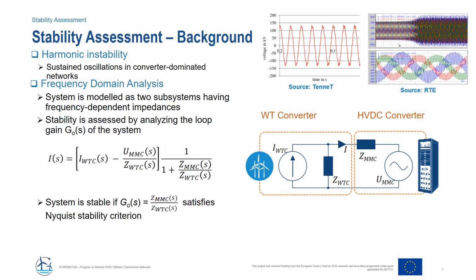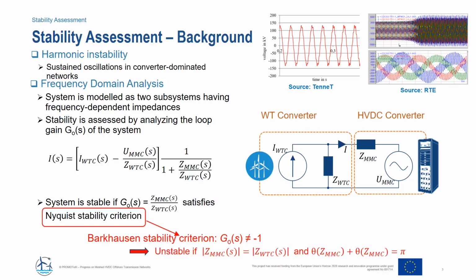The stability of the overall system is analyzed by the open loop gain G0 of the system. We say the system is stable if G0, defined by the impedance of the MMC divided by the impedance of the wind turbine converter, satisfies the so-called Nyquist stability criterion. In this implementation, we have simplified that even more to the so-called Barkhausen stability criterion. Basically, we say that the system is stable as long as G0 is not equal to -1. Furthermore, we could say that the system is unstable if the absolute values of these two impedances are equal to each other, and the sum of the phase angles is equal to pi.